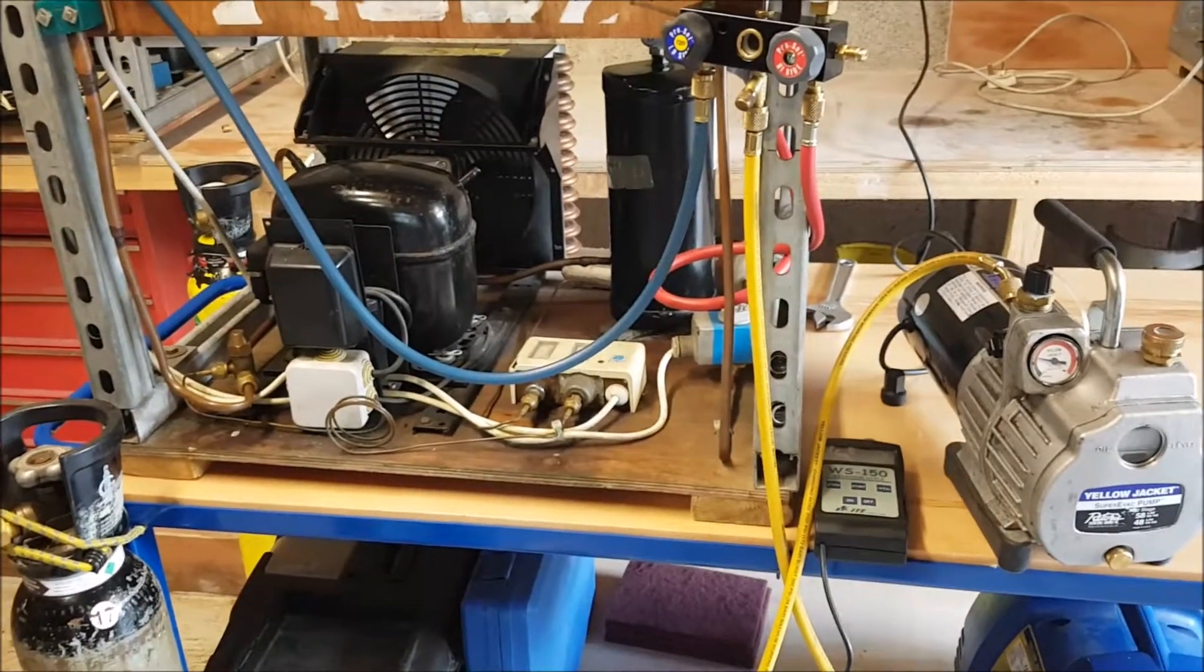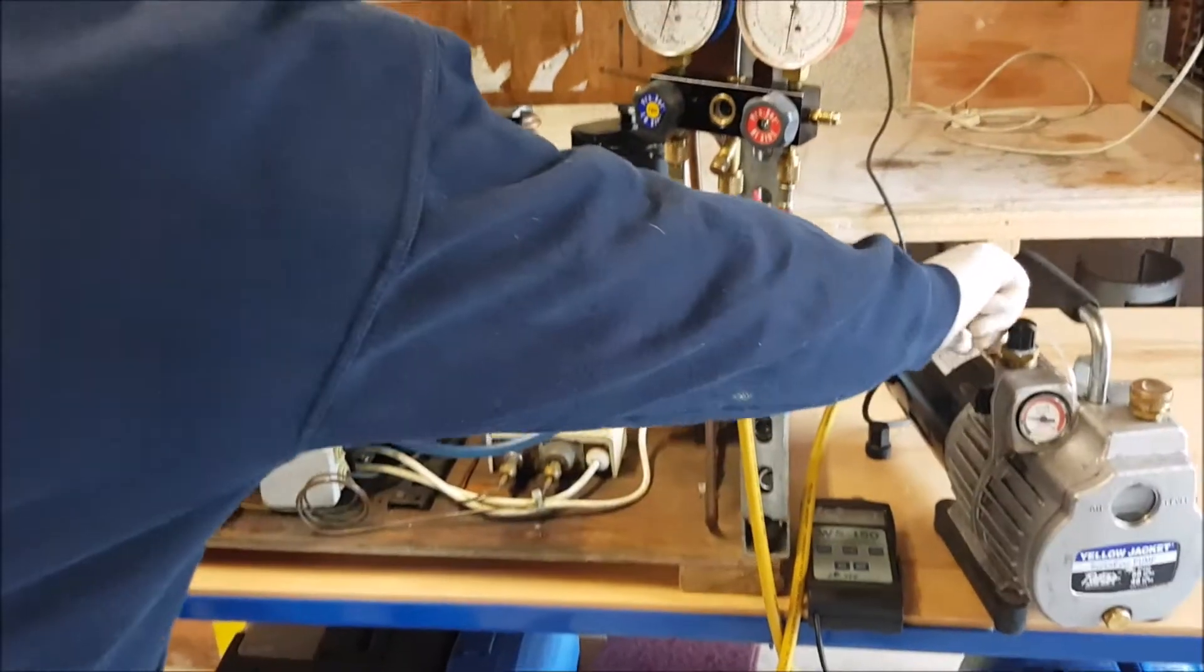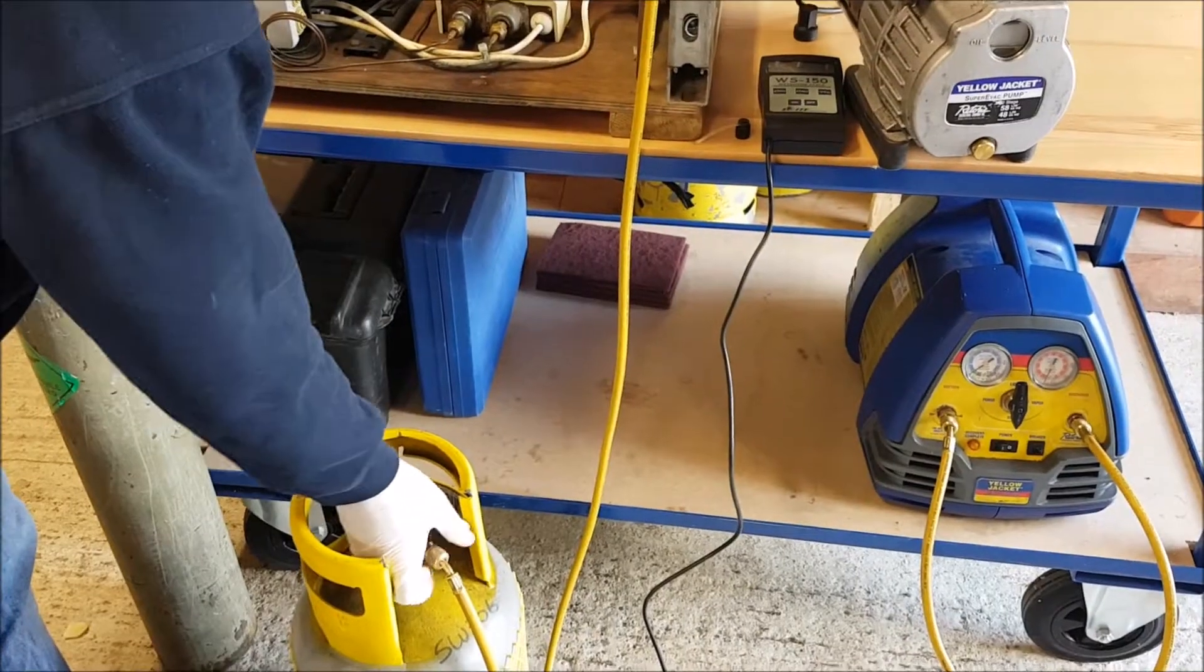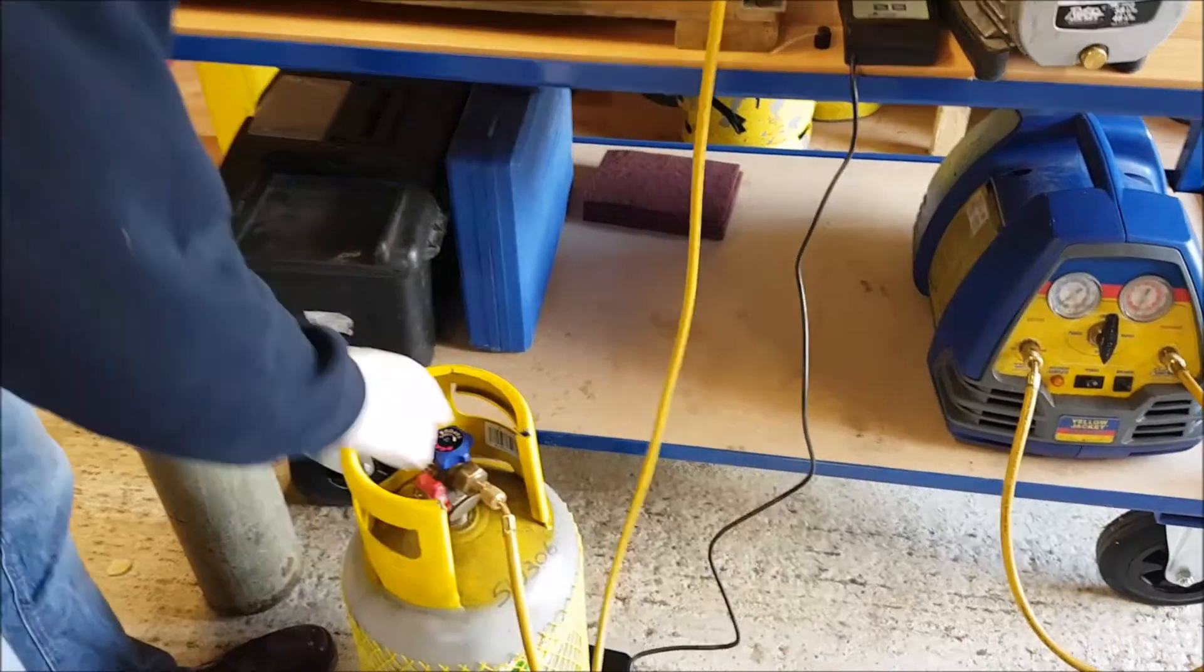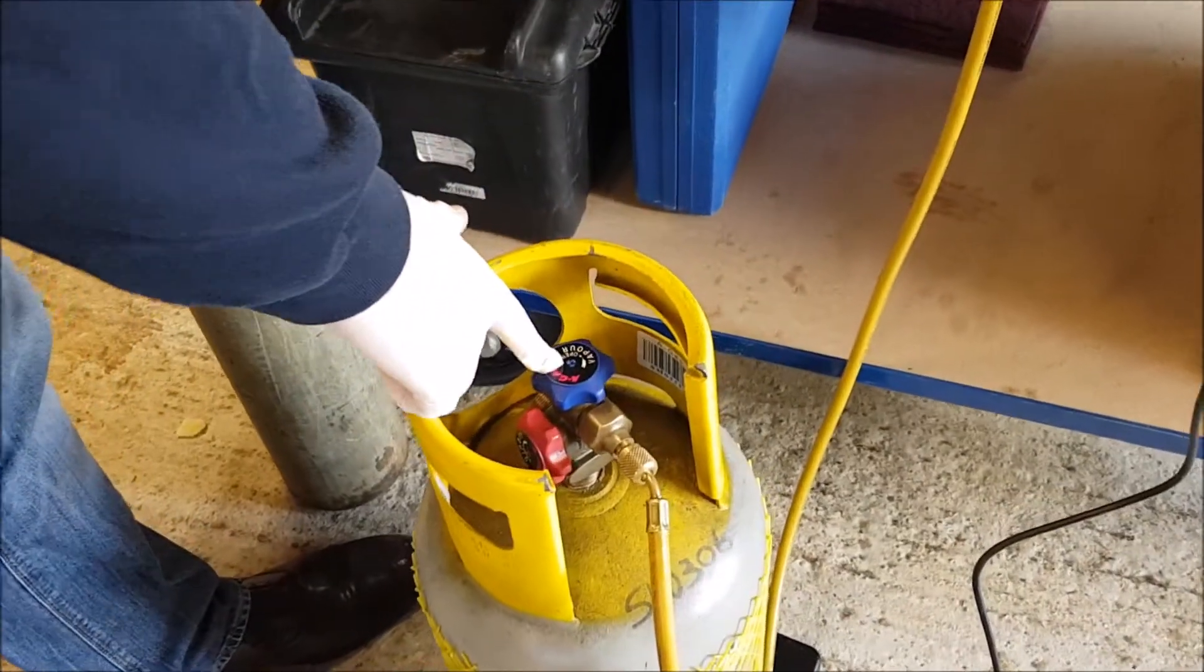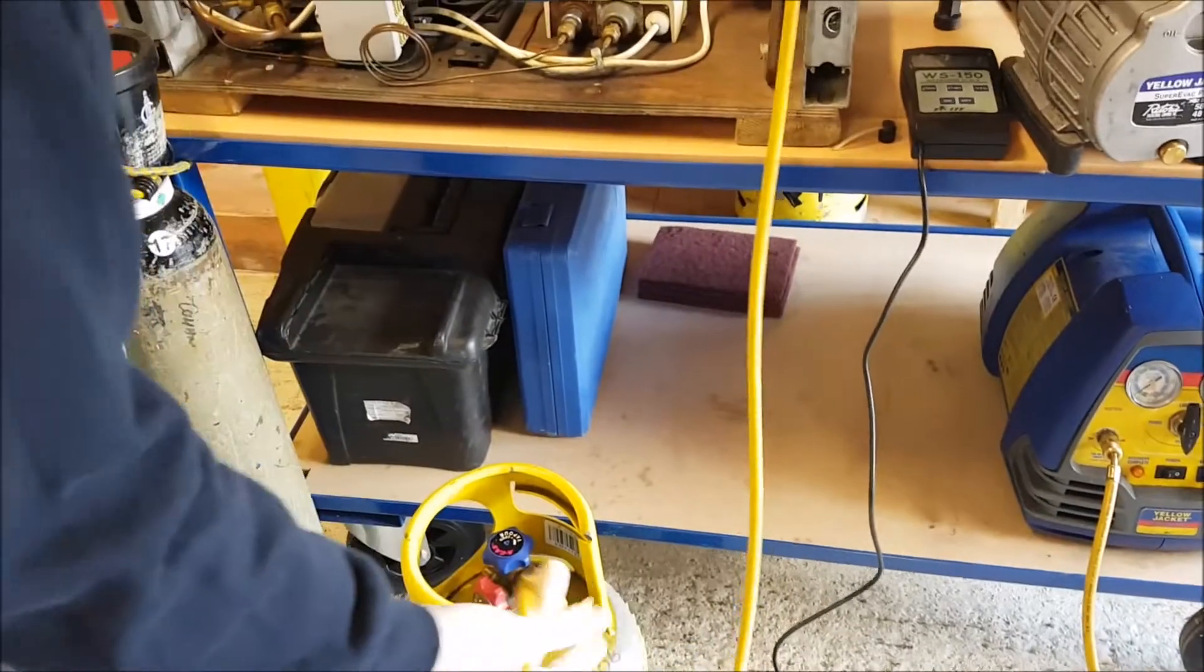The bottle when it's empty is 9.16. You take 9.16 from 10.54 and the difference is the amount of refrigerant that we have. Now, what I have done is I have connected my service hose to the vapor port here.